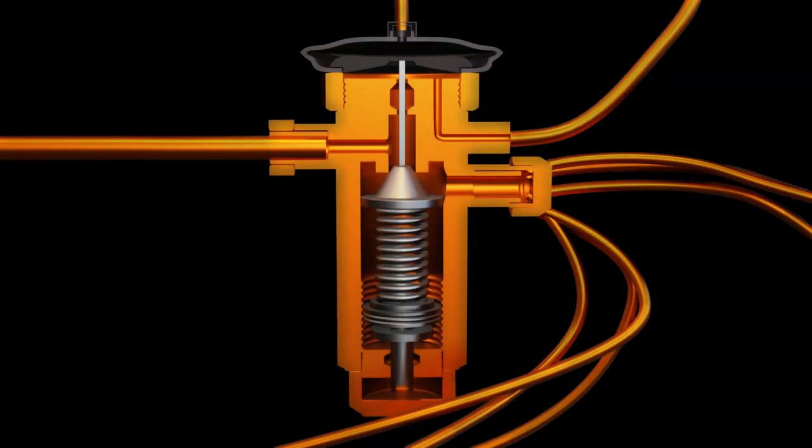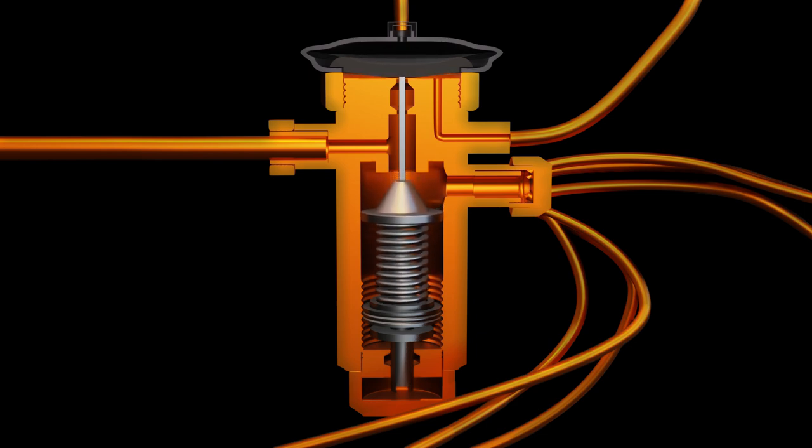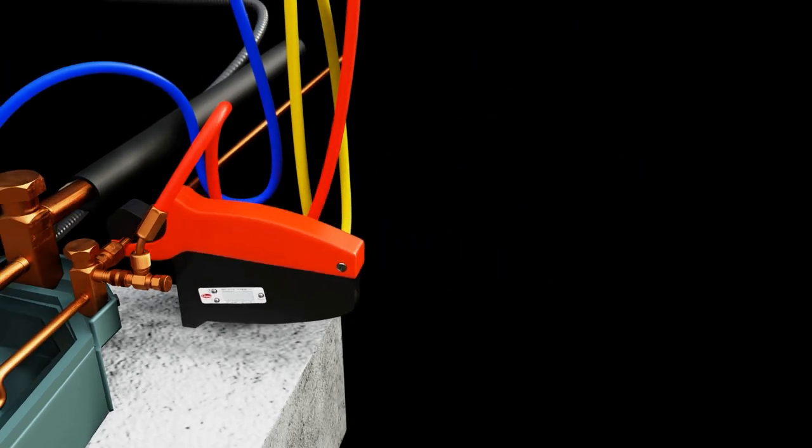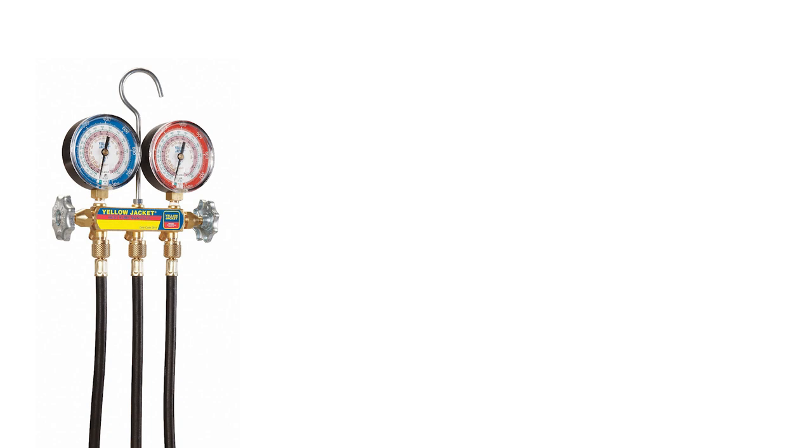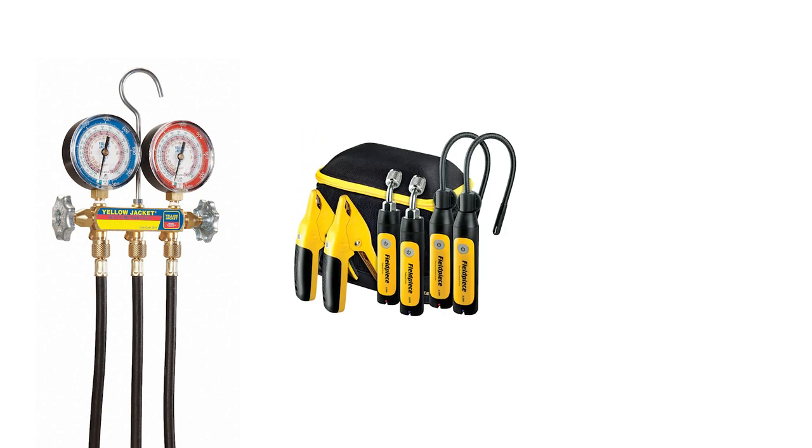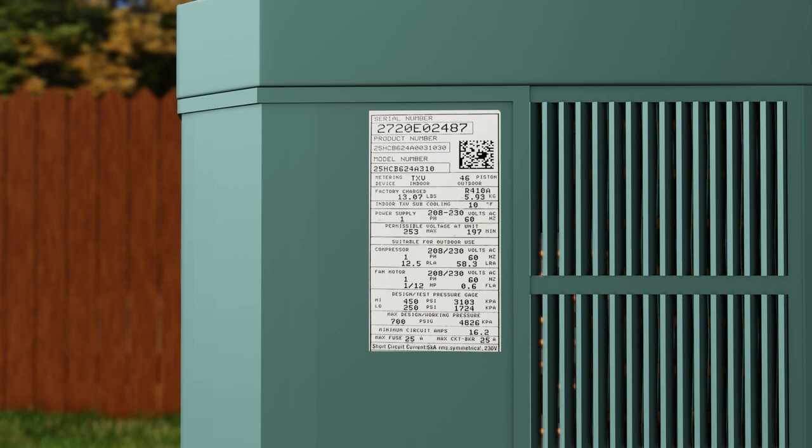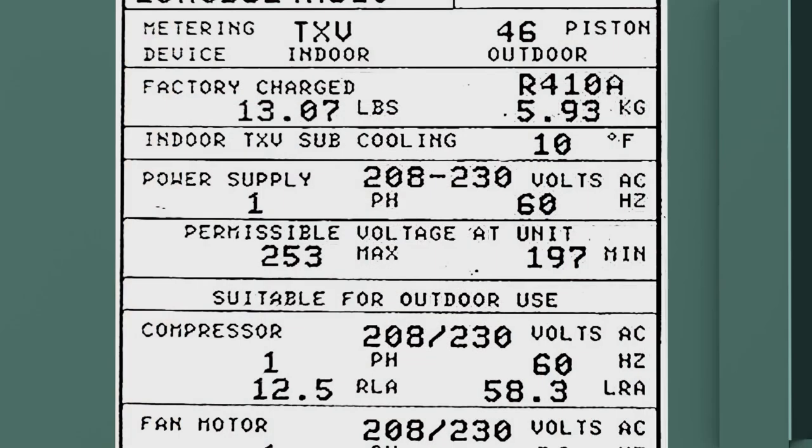We're going to just make the assumption this is a TXV system on the inside. You would actually have to check that to make sure that it is a TXV inside. We need to connect a line temperature clamp in order to measure our liquid line temperature. You can do this with either an analog manifold or with a digital set of probes or digital gauge. Because this is a TXV system, we need to check and see what our indoor TXV subcooling should be. That's the number that we want to hit.